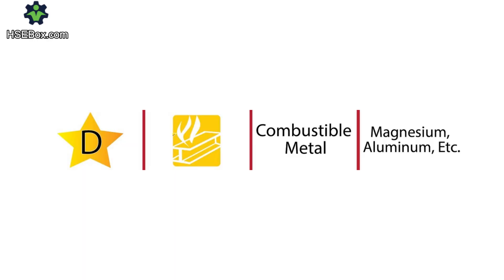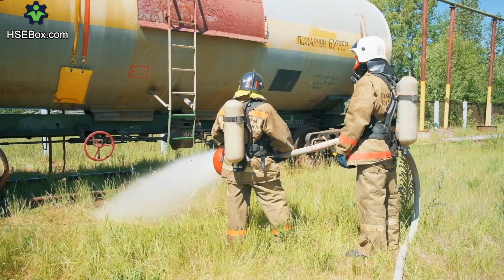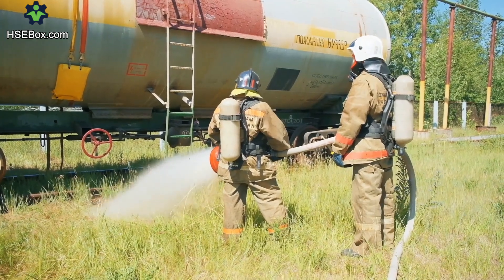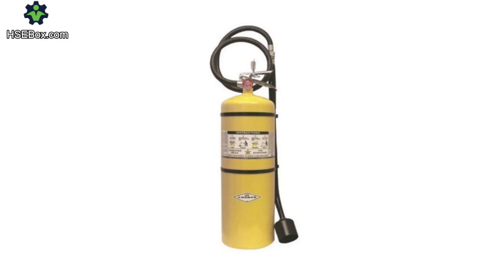Another less common but equally dangerous category is class D fires, which involve flammable metals like magnesium, titanium, or aluminum. These fires occur primarily in industrial settings and are particularly challenging to handle. Water and even foam are ineffective here, so dry powder extinguishers specifically designed for metal fires are used.